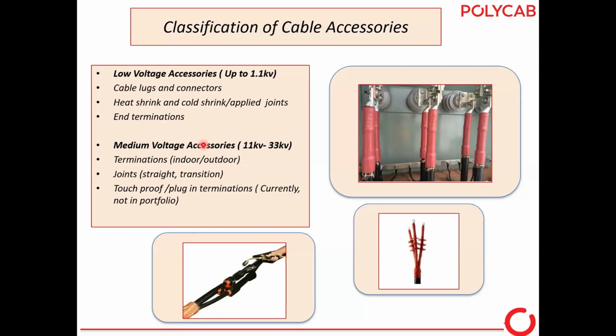For medium voltage, we classified again indoor termination, outdoor termination, joint, straight through joints, and transition joint. Transition joints are generally for one side XLPE cable, another side PILC cable, or different sizes of cables. So transition joints are also there. And for one of the projects, touch-proof plug-in terminations. Nowadays in metro cities, RMUs and GIS are used, so their specific type of terminations are required. That's a touch-proof termination. Some call it touch-proof termination, some call it screen termination.